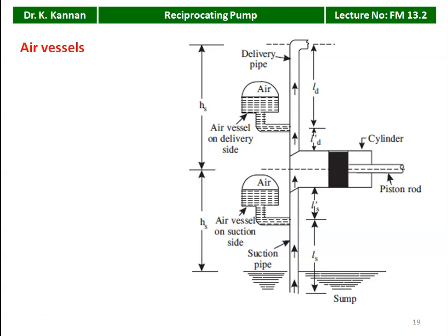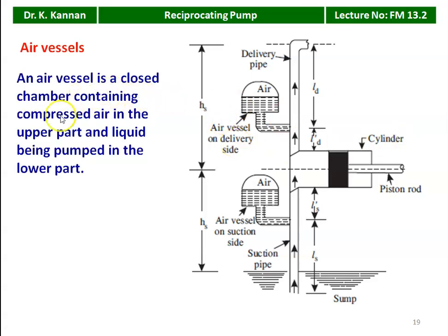In the single acting reciprocating pump, if we want a continuous supply of water in the delivery pipe, we install air vessels on the delivery side and the suction side. When you install the air vessel, the water will be delivered continuously. An air vessel is a closed chamber containing compressed air in the upper part and liquid being pumped in the lower part.